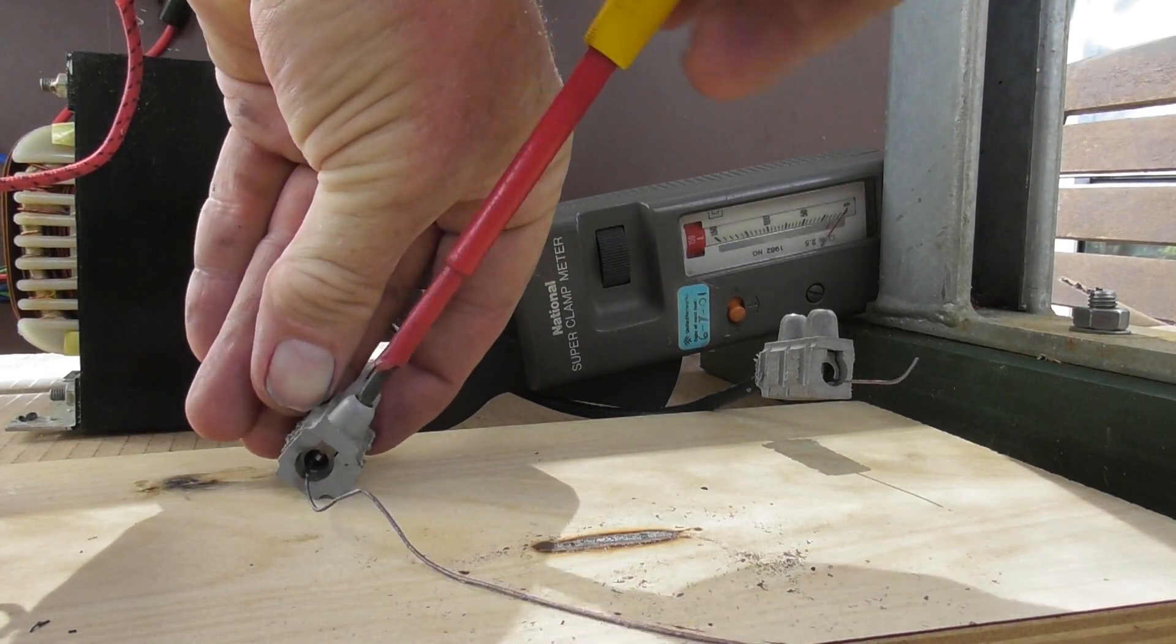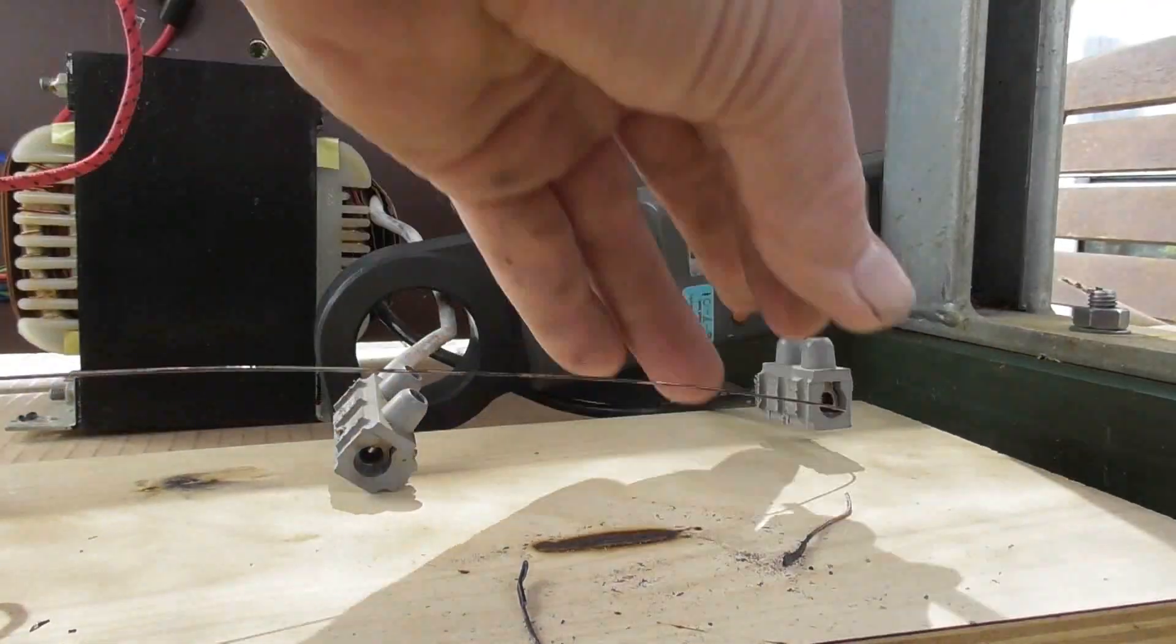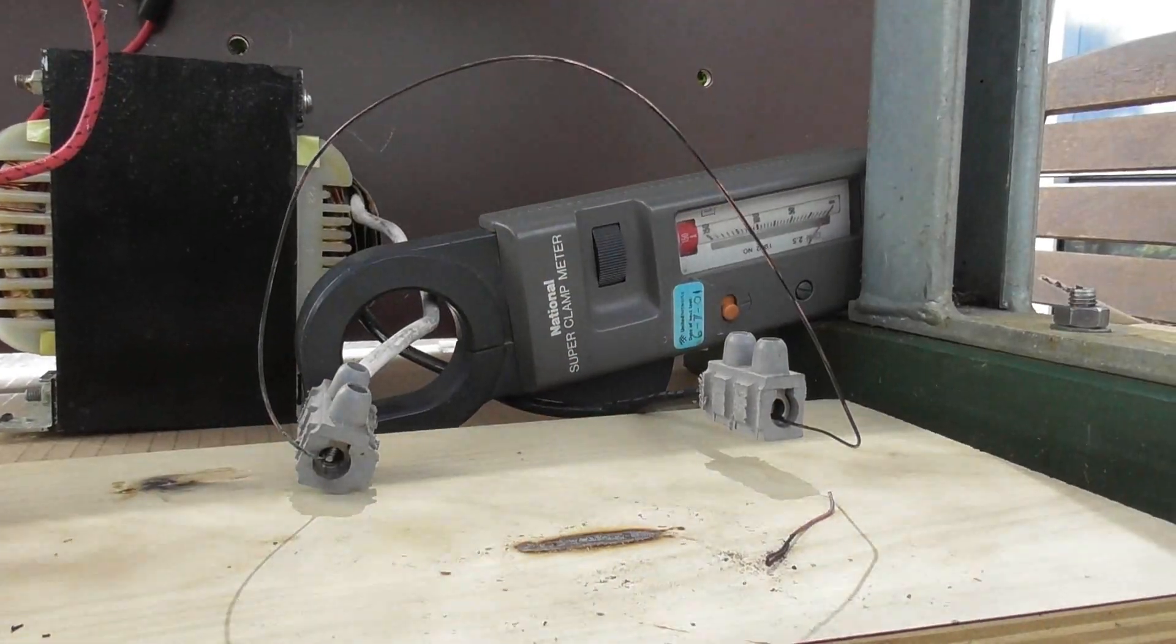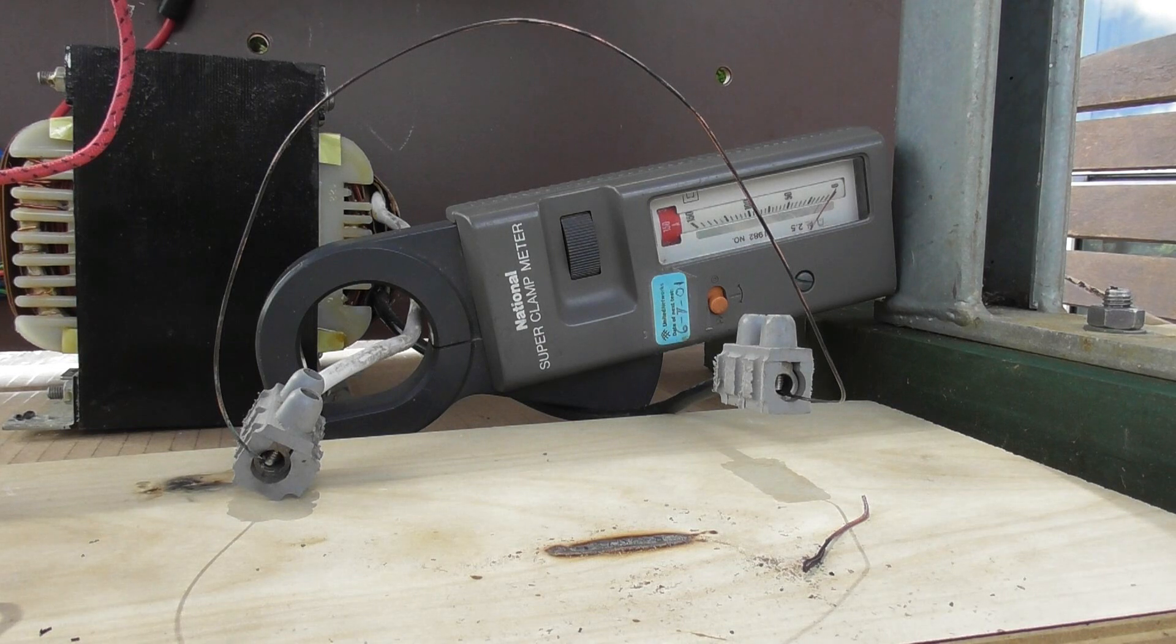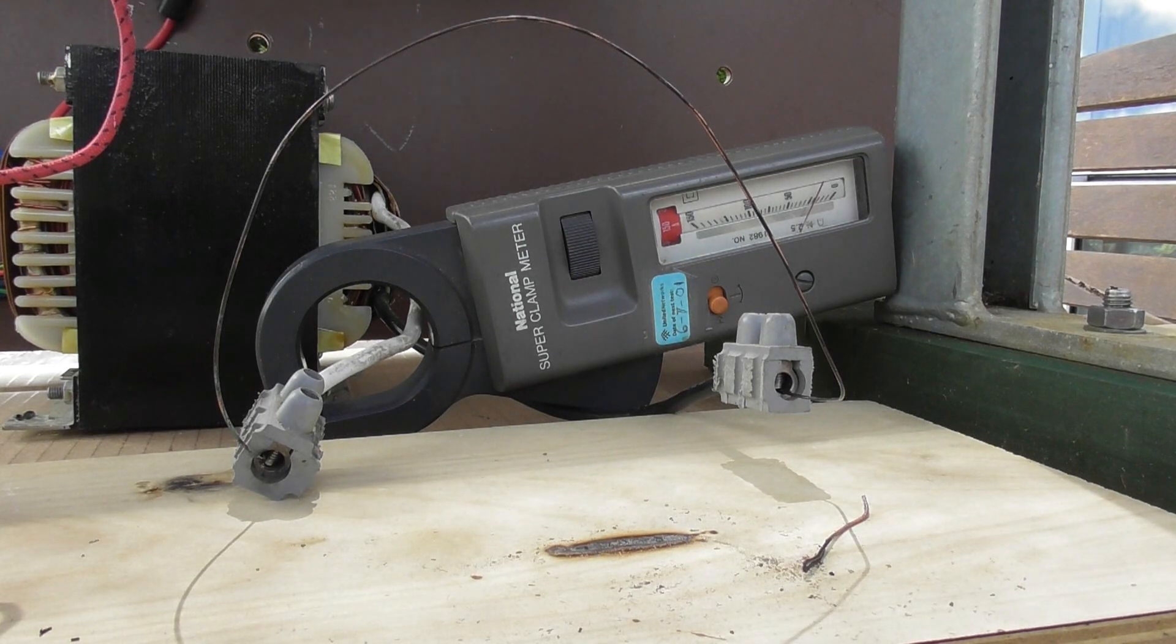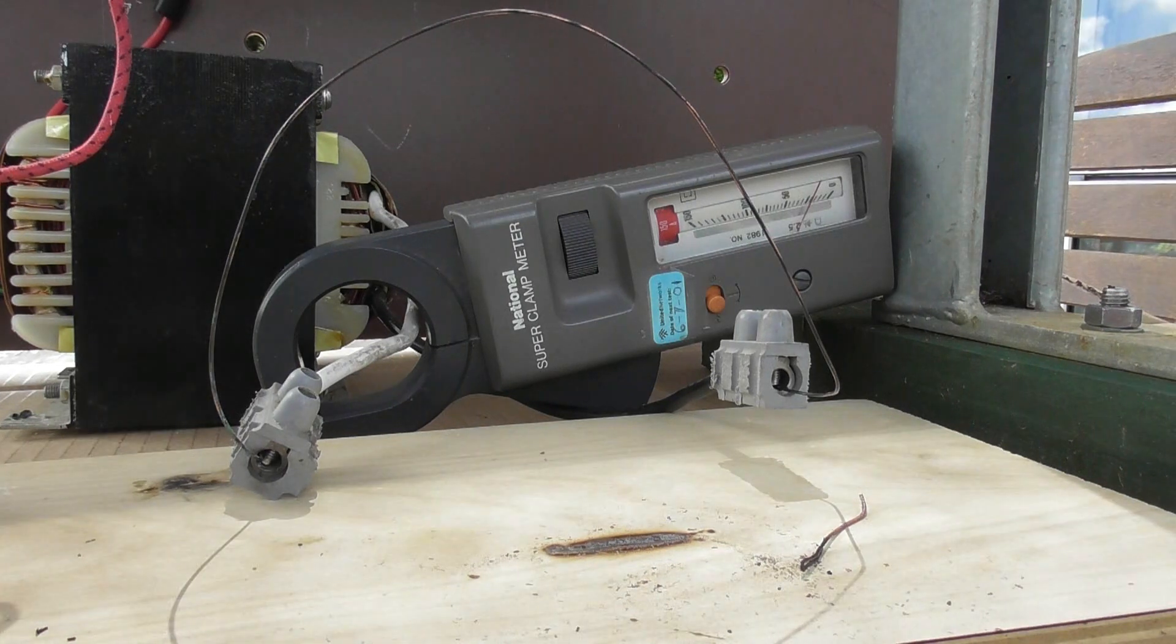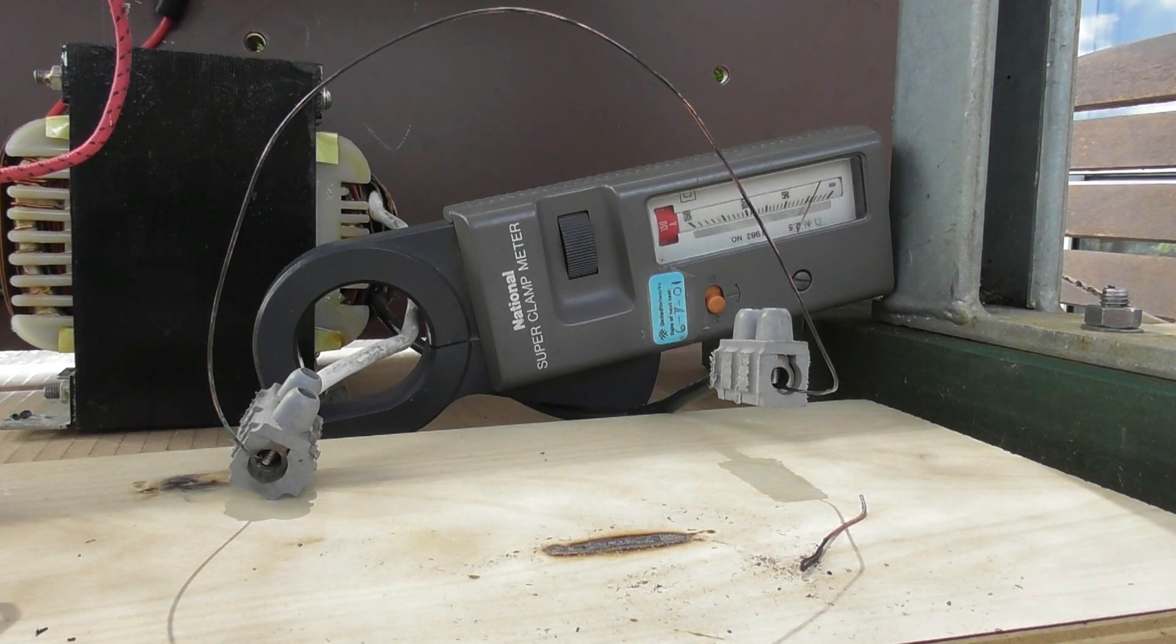Installed the new wire. As I said before, now we have an open secondary on the microwave, current should be less. Now the current is only about 25 ampere. So it's severely reduced. I'll de-energize and I'll short out the secondary. Standby.